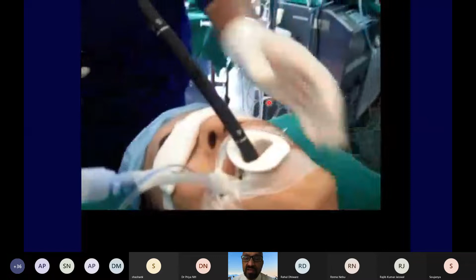Then coming to the standard words which are used, if the probe is pushed into the esophagus, it is called advance, and if you are pulling it out, it is withdrawal. The probe can be anteflexed, which means it is bent forwards, or retroflexed, which means it is bent backwards, by using the big knob on the control of the probe. We can change the multiplane angle from 0 to 180 degrees, which is called rotate forwards if you are increasing the angle from 0 to 180, or if you are decreasing the angle from 180 to 0, it is called rotate backwards. The probe also can be flexed right or left by using a small wheel on the knob, and this is called flex to the right and flex to the left.